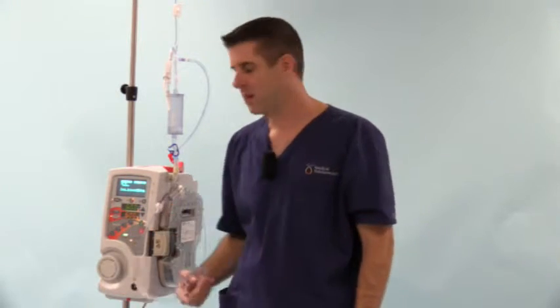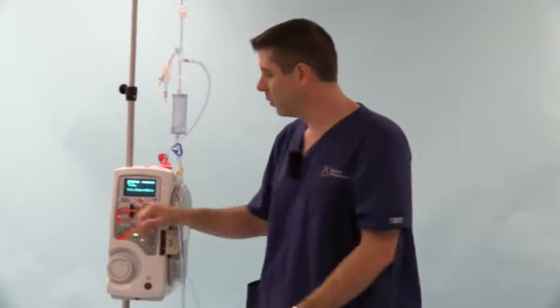The next area we'd like to talk about is patient line blocked errors. Now with this system, we've got the most advanced pressure control system available with multiple pressure sensors that are constantly monitoring pressure in the patient line and reducing flow rate to stay under your designated pressure cap. With that, though, there are some factors that may cause a patient line blocked error if you're not cognizant of them. Although you can use the system with any size catheter, it's more susceptible with smaller catheters.